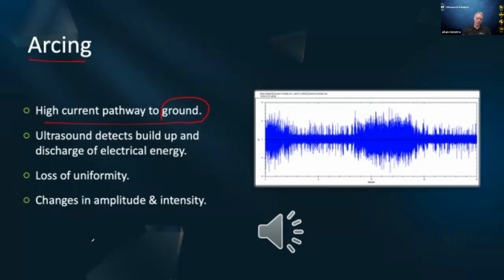But man, if you're a rookie to ultrasound, if I was hearing that for the first time, I'd just say it sounds angry, and nobody wants an angry asset. If we've reached the point of arcing, we're now in the danger zone, and it's arcing that's going on inside cabinets, which can mix with air and then create that arc flash when we open the panel.